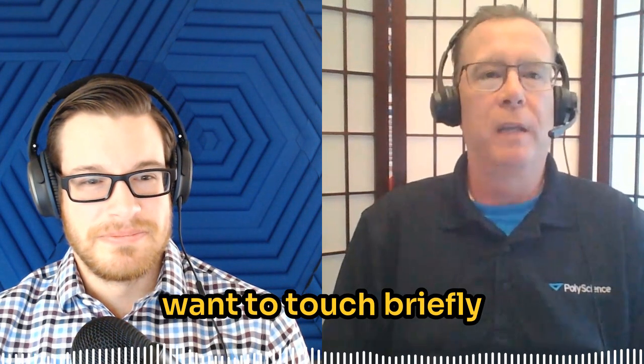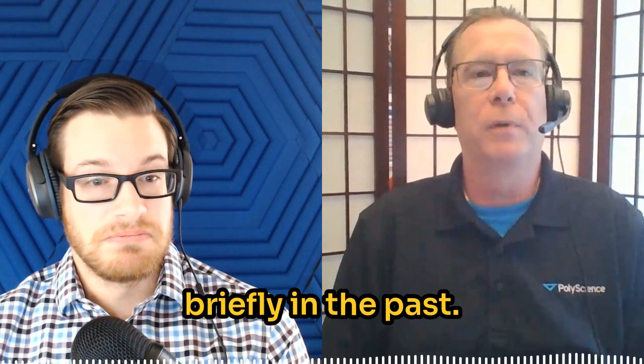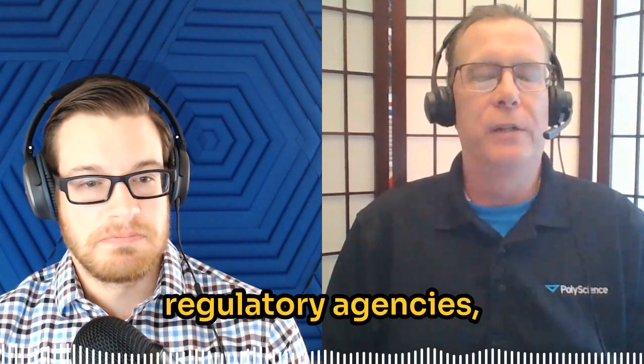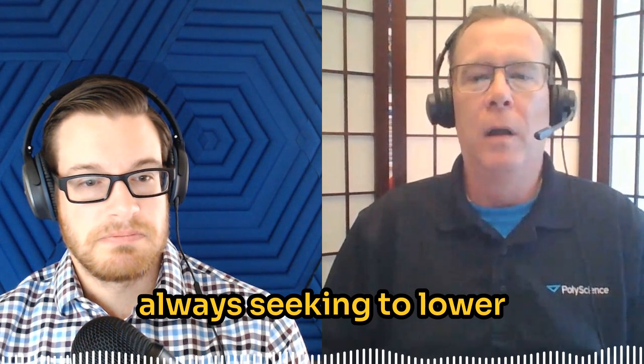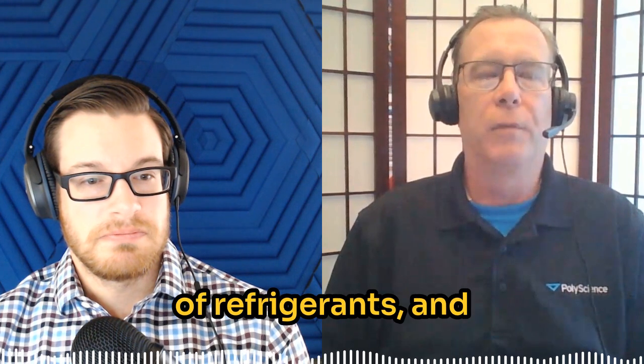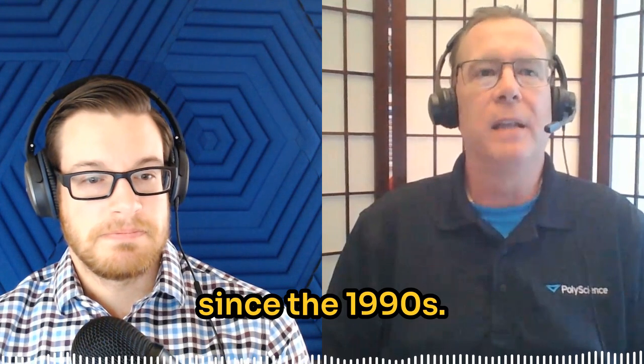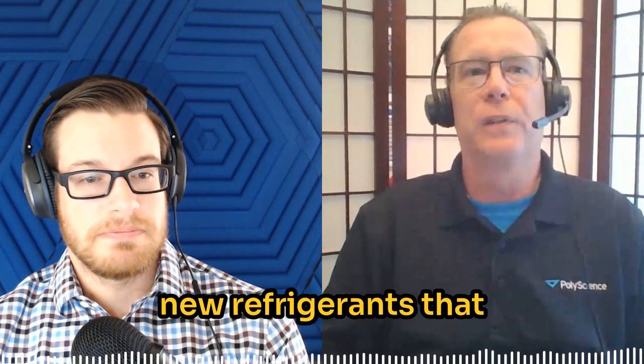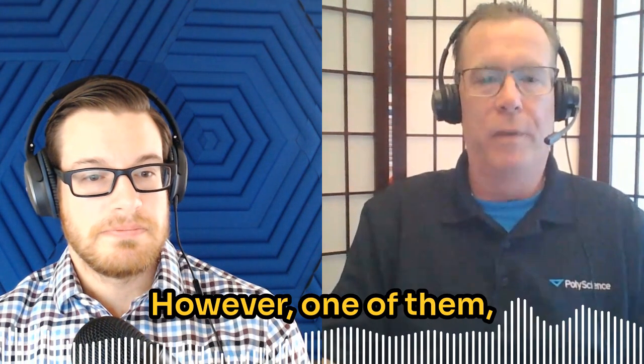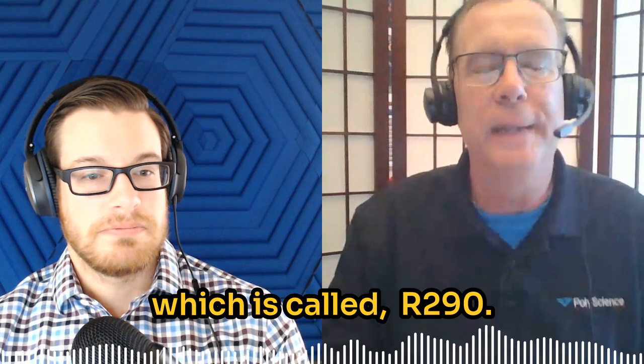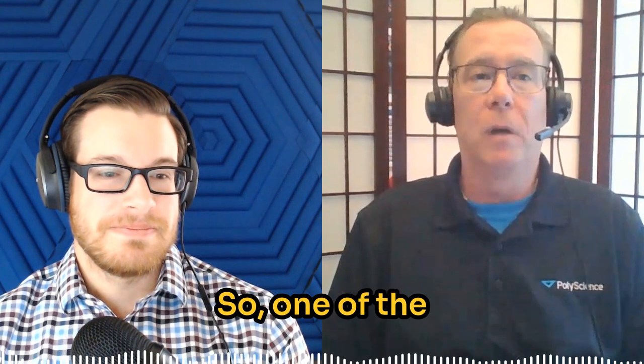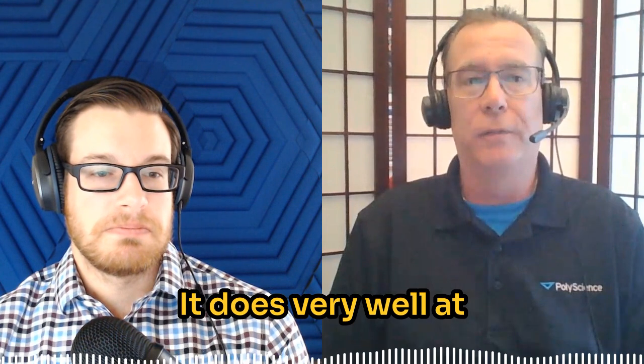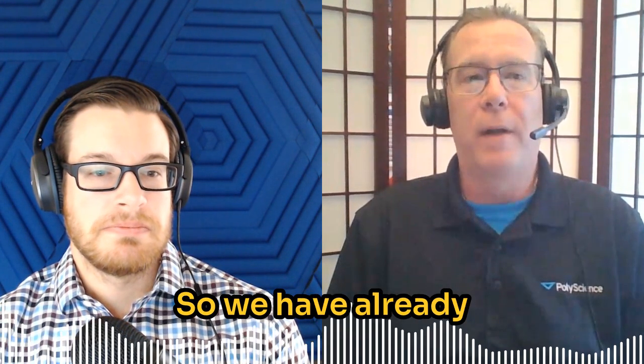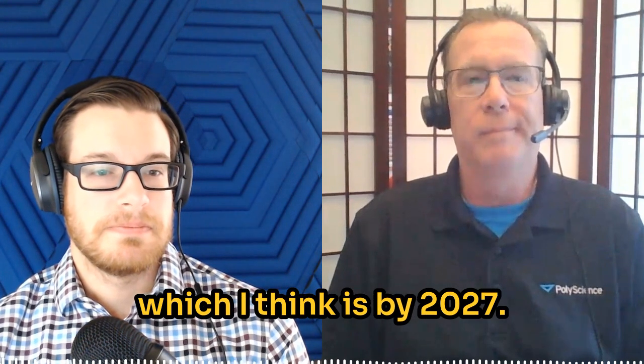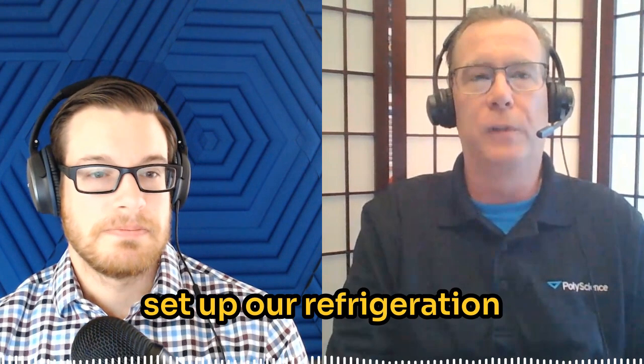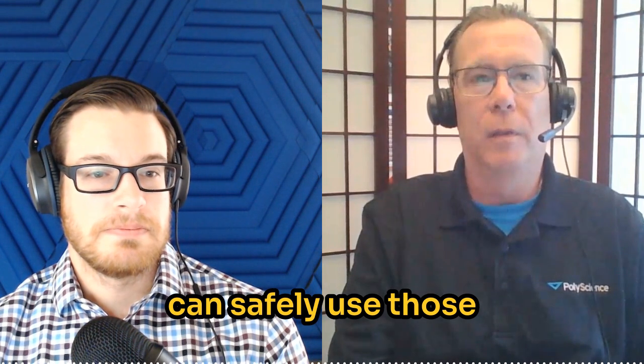I also wanted to touch briefly on the changes coming in refrigerants. Due to European regulatory agencies and the EPA, there's always a push to lower the global warming potential of refrigerants, and that's been happening since the 1990s. Now it's getting to the point where these new refrigerants are very environmentally friendly. However, one of the main ones we'll be using, called R290, is actually a refrigeration-grade propane. It's a great refrigerant, but it's flammable. Knowing we'll have to move to this—by around 2027, I believe—we've already set up our refrigeration assembly so we can safely use those flammable refrigerants.